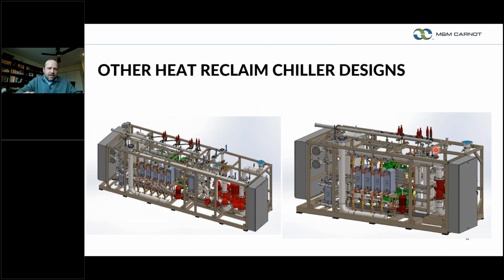I just wanted to show you examples of industrial CO2 industrial refrigeration chillers. These two, I'm showing the heat exchanger sides of the chillers, but these heat exchangers can be selected for various temperatures and different applications based on a constant cooling load. So cooling's first, and then you're reusing that heat second when you can.